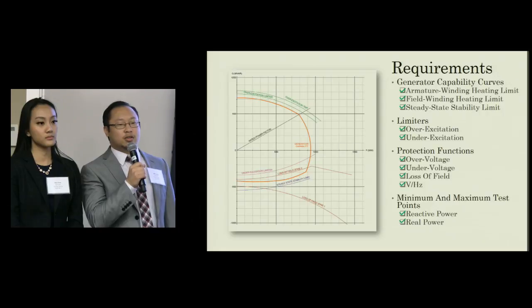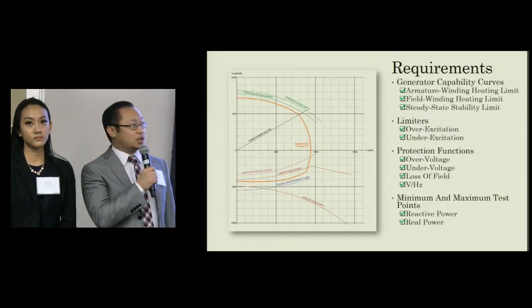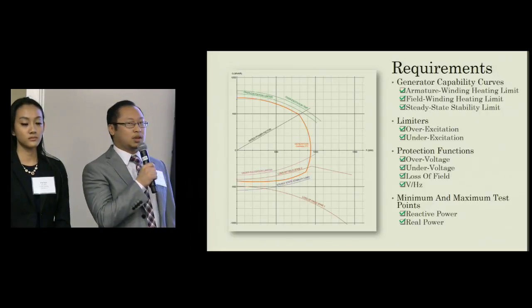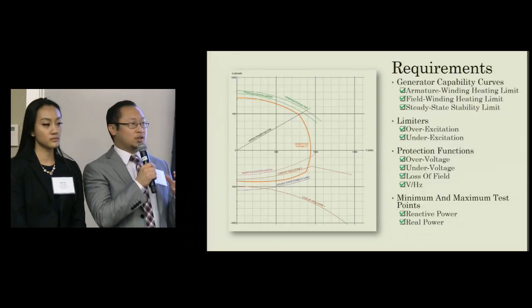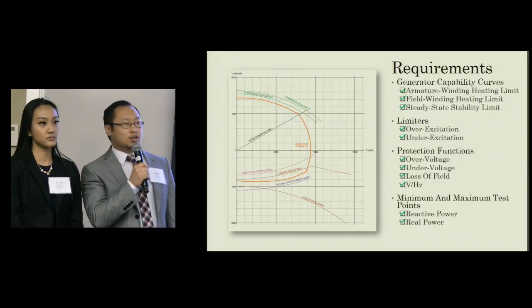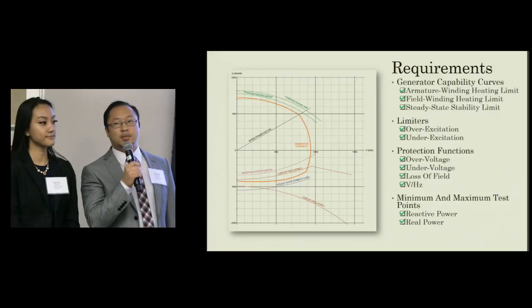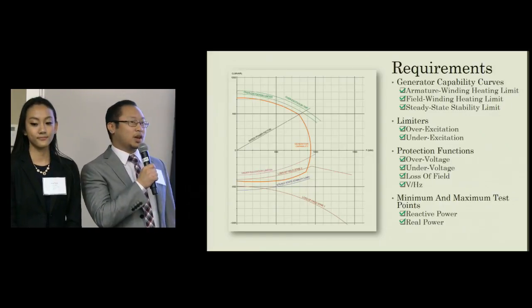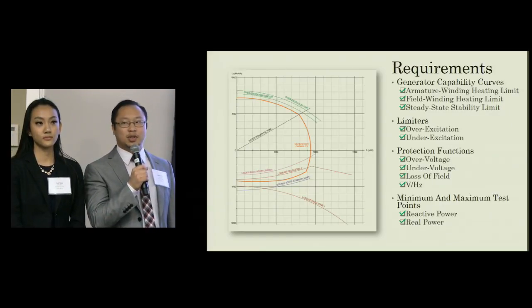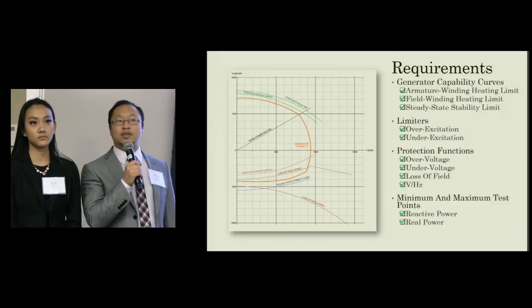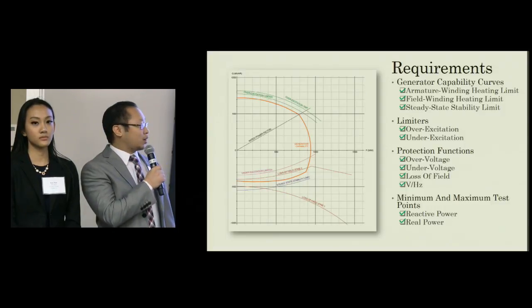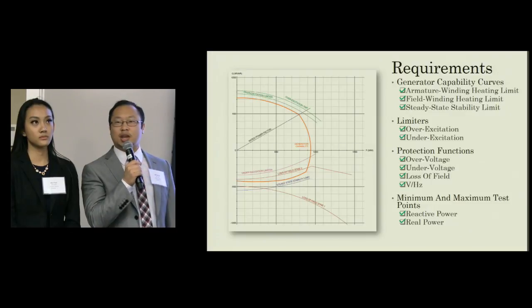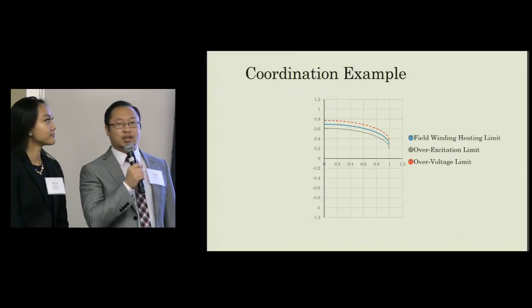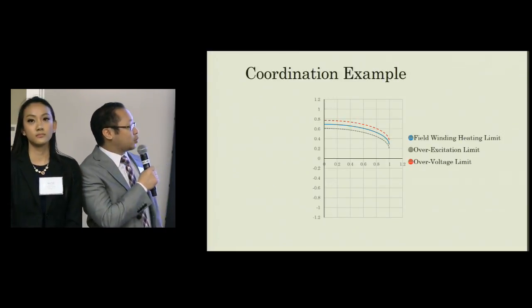Volts per hertz monitors the voltage and the frequency of the output and makes sure that the ratio stays the same. Finally, our tool is able to plot the minimum and maximum real and reactive power capability test points, which represent the power capability of the generator when it's running, or based off a test done by Chelan County PUD. Here's an example of a coordination that might be done with our tool.